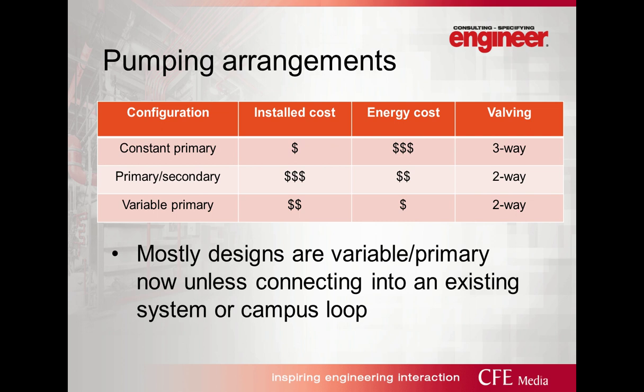Your valving in the system — where the load occurs at the air handling units — can vary between two-way and three-way valves, which is important to note when doing renovation projects. In most new designs, we are designing them to be variable primary, as it is becoming the most efficient approach and is also good from an initial installed cost perspective. Water-cooled systems are typically seen in large commercial buildings, campus distributions like universities, healthcare applications, labs, and data centers — mostly buildings with 24/7 operations where the payback is quick due to system efficiency.